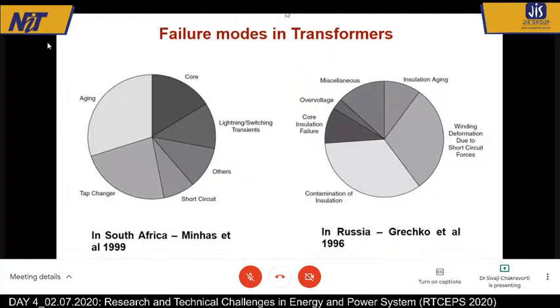Then if we look at the failure modes in transformers, on the left-hand side diagram is a study in South Africa showing the different failure modes. You can see that the largest block of the pie chart is aging, and when we talk about aging, it is the insulation.